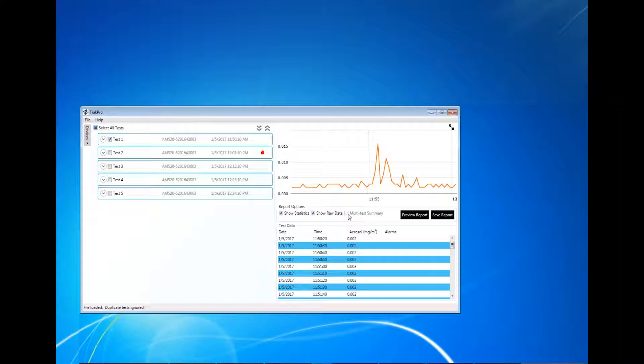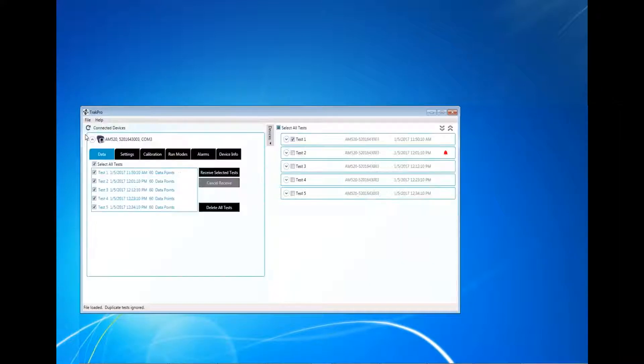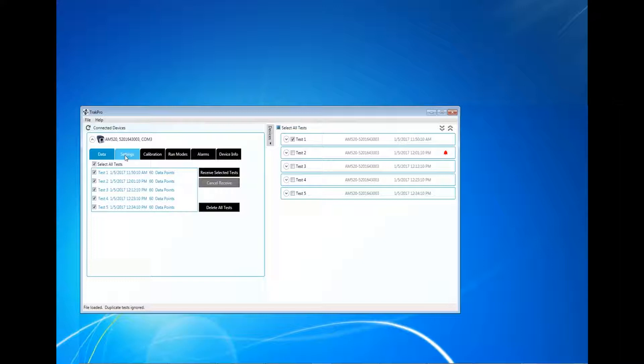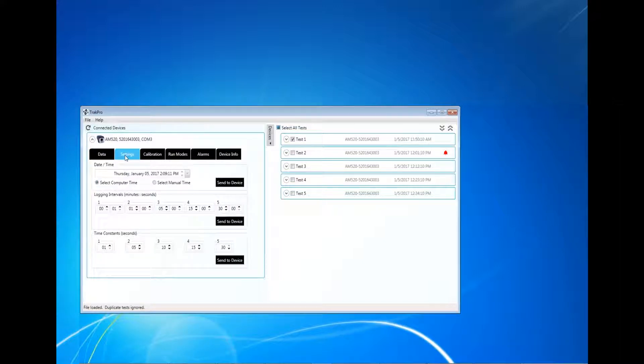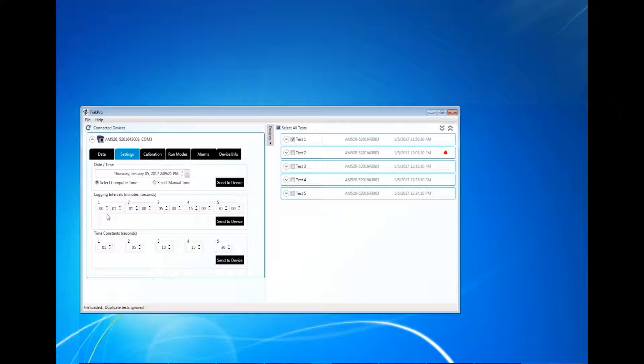The Settings tab allows the user to configure the instrument's date and time, logging intervals, and time constants. The date and time can be changed to match the computer it is currently connected to, or by manually entering a time in the above field, selecting Manual Time, and clicking Send to Device.